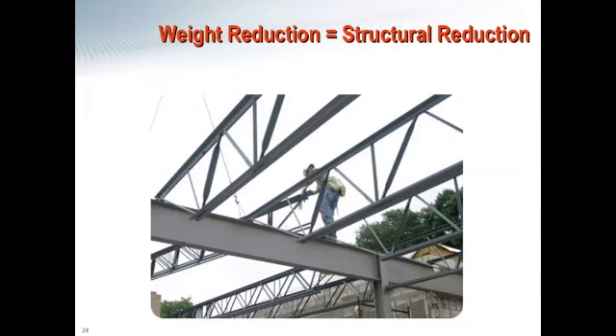So for example, rather than having a giant rooftop unit sitting in a centralized location on your roof, you can have 5 different smaller rooftop units with VRF, positioned out towards the corners or in areas where there's already dunnage or existing structural support. And in a lot of cases, it's really able to minimize the amount of retrofit support you're going to have to add to a project. That's going to save on installation costs, and save on total project costs. And that's one of the main drivers of VRF over a lot of traditional systems as well.